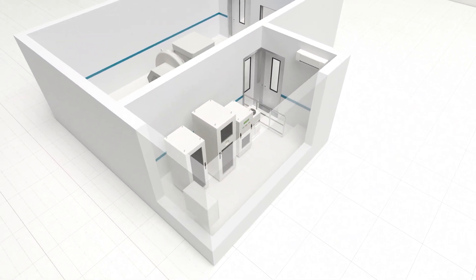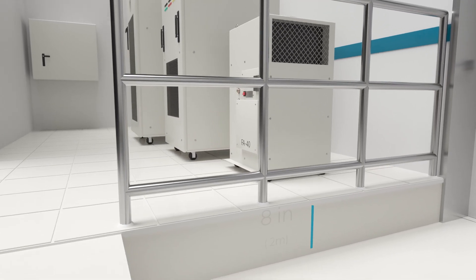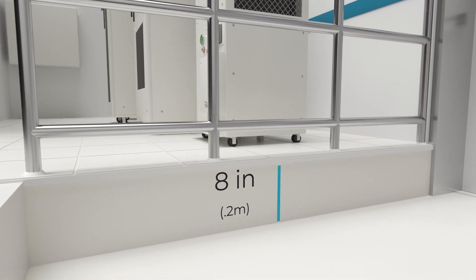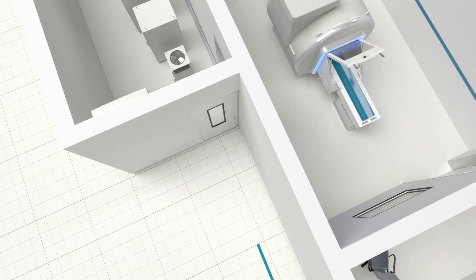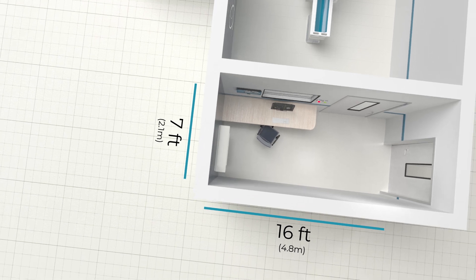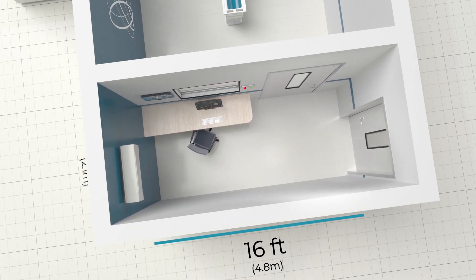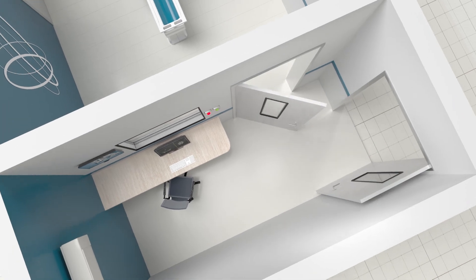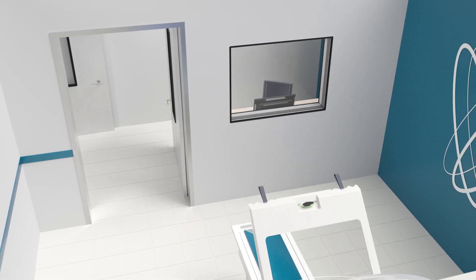Our standard equipment room measures 16 feet long by 8 feet wide and utilizes an 8-inch computer subfloor to safely cover a multitude of high voltage power cables. Our typical control room measures 16 feet long by 7 feet wide and ideally is large enough to allow a non-ferrous patient gurney to enter the scanning room through the control room access door.